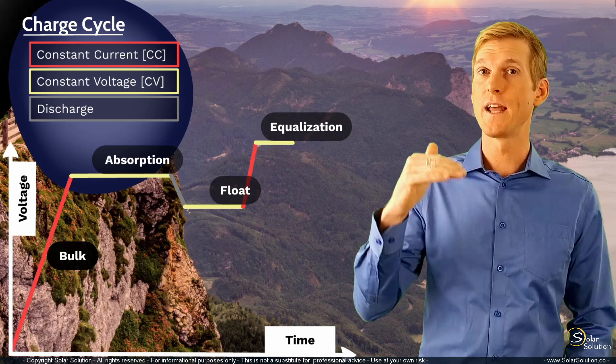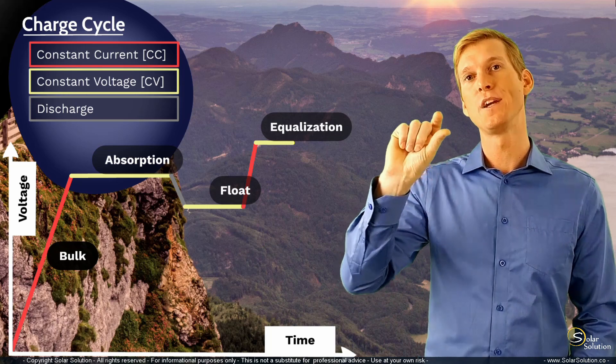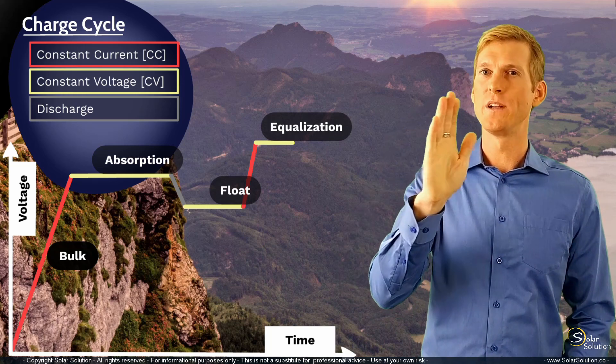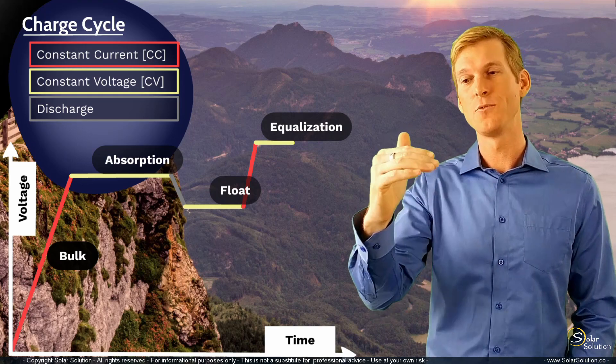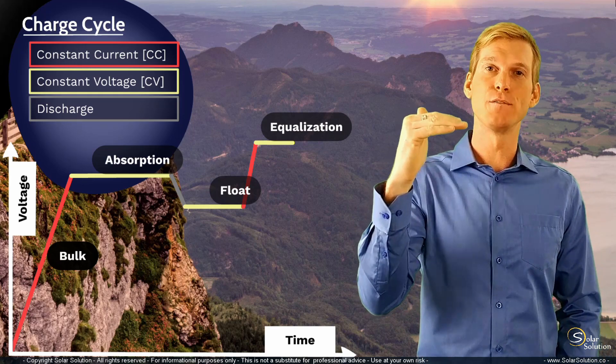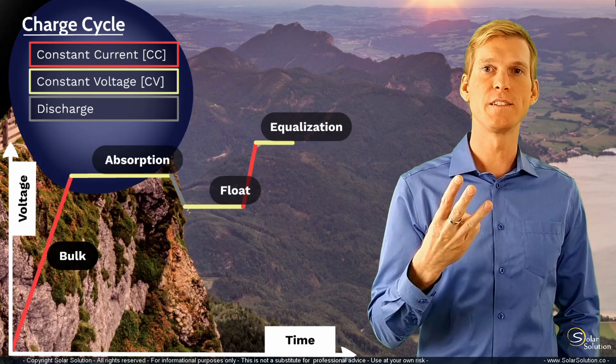Then once you have reached this elevated voltage, so the equalization voltage, the charger will change its behavior, the same as when it changes from bulk towards absorption. So it changes from the red towards the yellow line, it will now maintain the equalization voltage for a set amount of time.